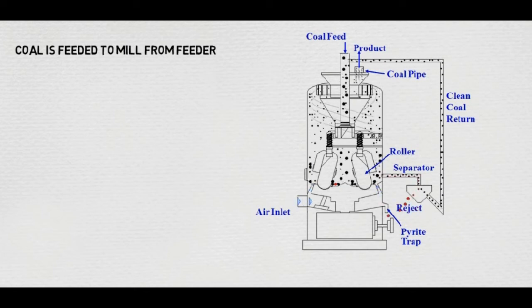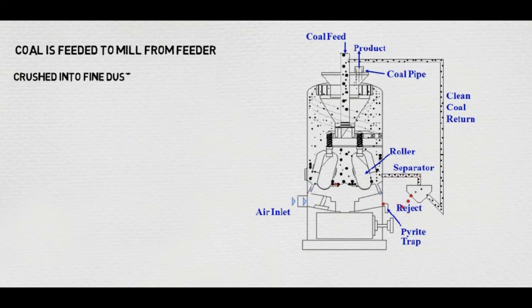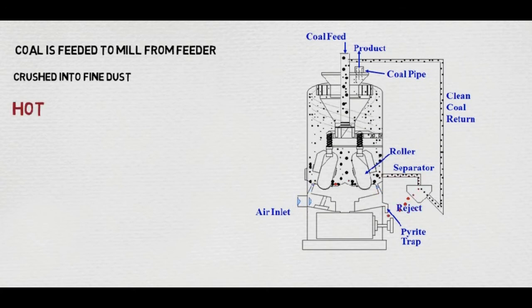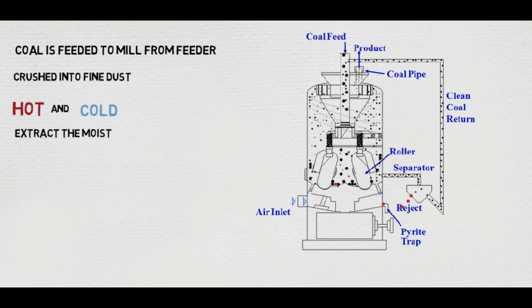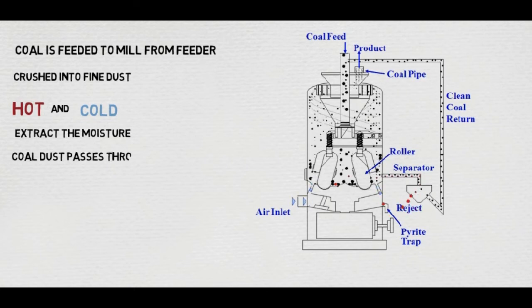The coal enters into the mill from the feeder. The roller is used to crush the coal into fine dust, and the waste material goes into the MRS, which is the mill rejection system. By the separator, the mixed airflow — that is, the hot and cold air — enters into the mill for extraction of the moisture contained in the coal.